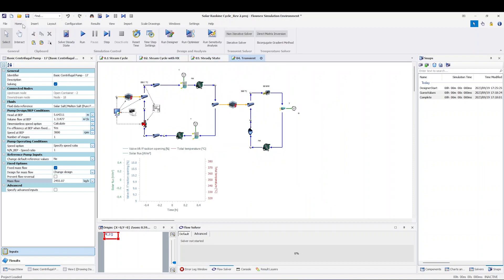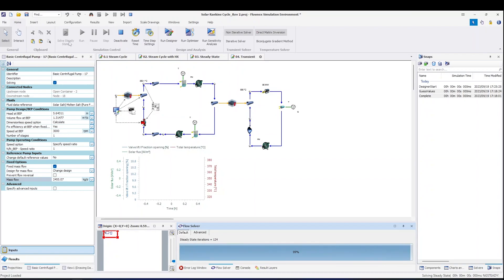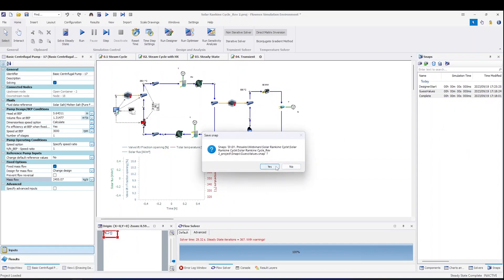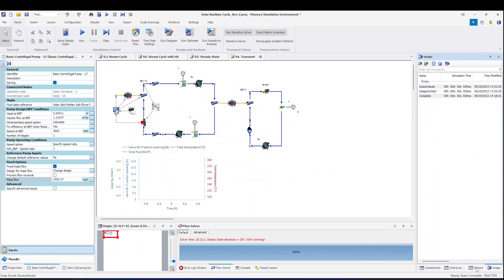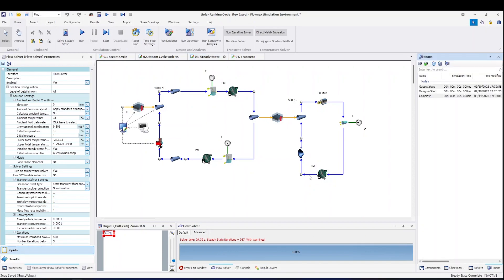Moving to transient simulation, I added a velocity PID controller for the valve to control valve opening and maintain the desired outlet temperature. I deactivated some drawing sheets to obtain the steady-state solution first, which is much easier with most sheets disabled. I saved a snapshot of the guess values and configured Flownex's flow solver to initialize from that snapshot — reducing the steady-state solve to just 17 iterations.